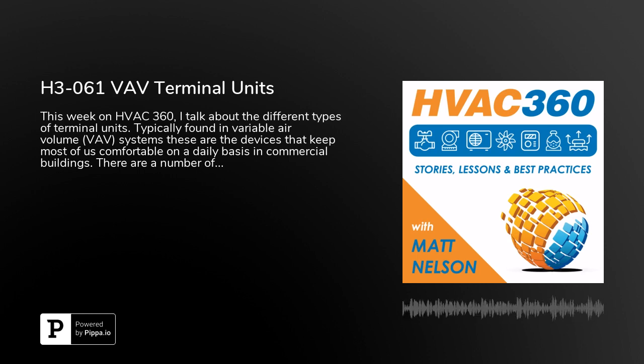Now, if you talked about the deluxe Cadillac system, when you're talking about the constant volume system, it was the dual duct. When money was no object, they would put in a heating duct run, and then right next door they'd have a cooling duct run, and it was a constant volume at the dual duct box, and it would constantly blend this combination of hot and cold air, and it would transmit that to the space at a constant volume. And I mean, you got exactly the temperature that you wanted. But obviously the problem is you're simultaneously heating and cooling that air, so that was kind of an issue. And again, you just had the same airflow regardless of what temperature you wanted, and you didn't have any savings on the fan horsepower side, so to speak.